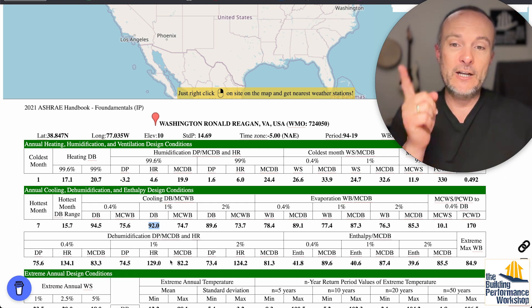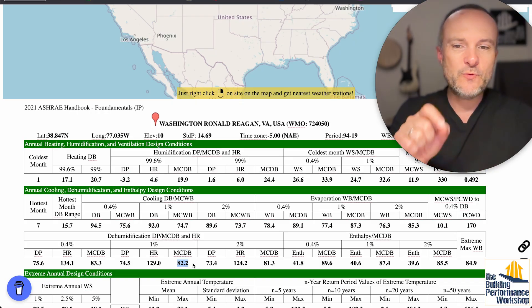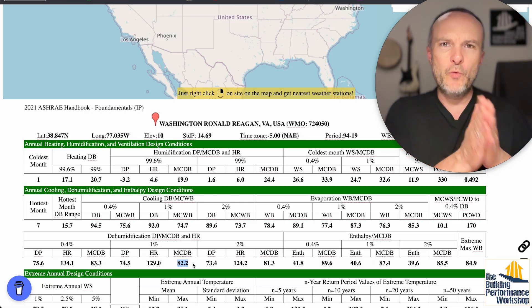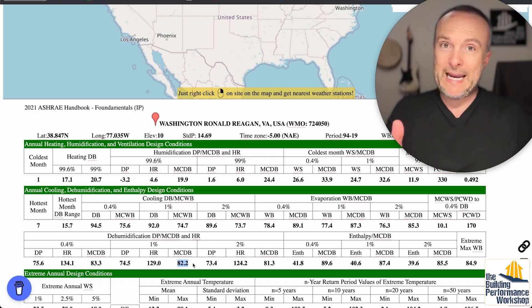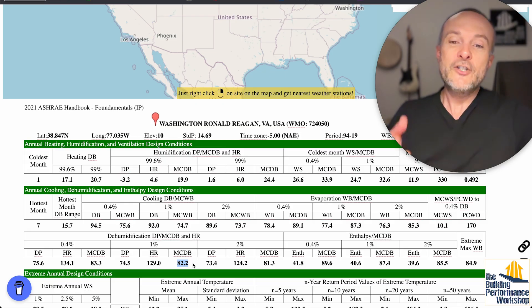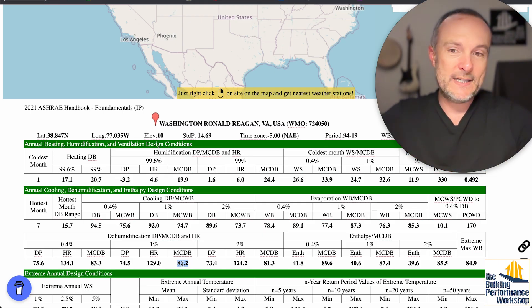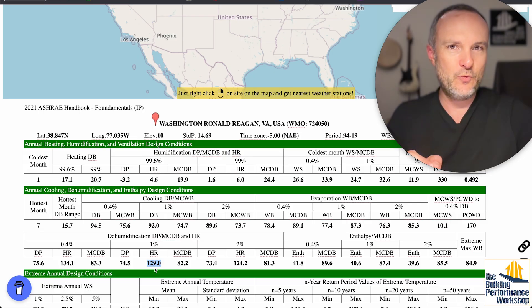What we then want to do is take this number and look diagonally right down from it. 92 degrees hottest, 82 degrees wettest — that is where there is the most moisture in the air. We thought for about 100 years that the hottest temperature was also when there was the most humidity, because relative humidity is relative to the temperature and warmer air can hold more moisture. But what ASHRAE found when they actually started measuring in the 1990s is that's not what happens at all. There's a 10-degree difference between the hottest and the wettest temperature in Arlington, Virginia, and at that wettest temperature we have 129 grains of moisture per pound — that's absolute humidity. Relative humidity is mushy because it's relative to the temperature, so we can't really use that.